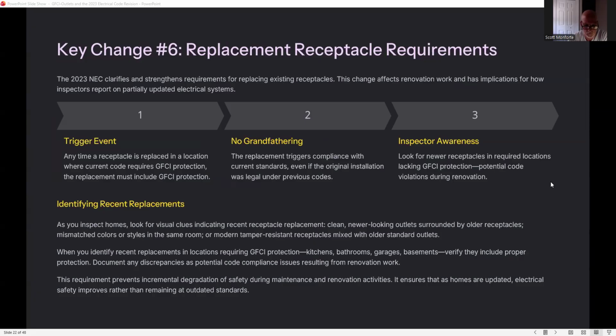So number 1, trigger event. Anytime a receptacle is replaced in a location where current code requires GFCI protection, the replacement receptacle must include GFCI protection. No grandfathering. The replacement triggers compliance with current standards, even if the original installation was legal under the previous code. Inspection awareness: look for newer receptacles in required locations lacking GFCI, potential code violations during renovation. So if we're going into a basement and we see brand new outlets because the old ones were kind of crappy and they're not GFCI, they're no good anymore.